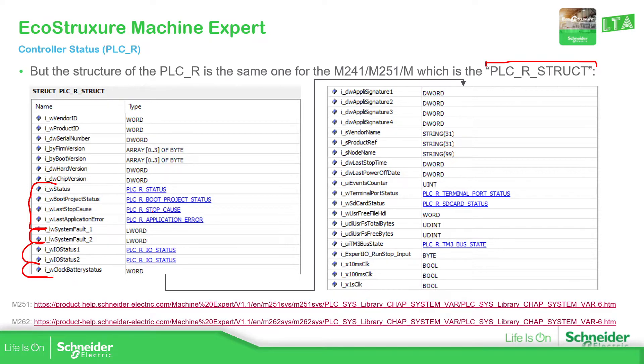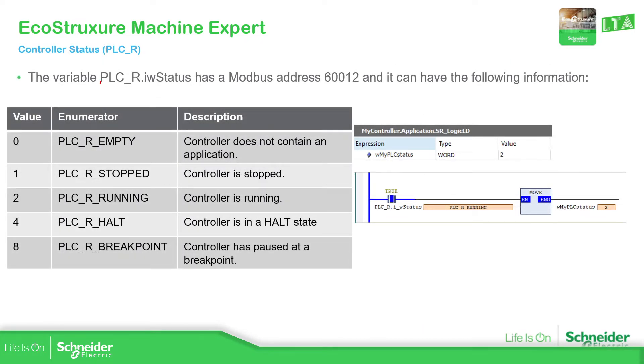So you have this information available once you are, for example, in the watch, or you want this variable in your program. The important one is PLC underscore R dot IW status, which is the status of the controller. This is the enumerator that it's using. So depending on the value that it has, it gives us this enumerator. You can see over here that you can find the status of the controller: it's empty, stop, run, halt, and breakpoint.